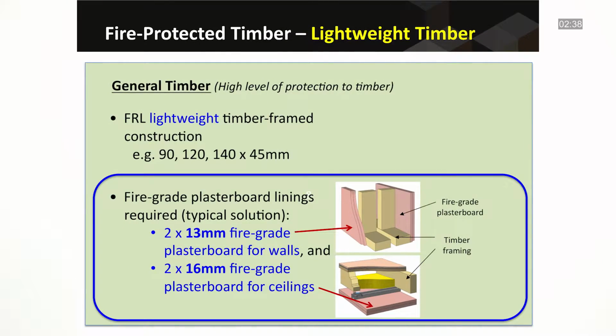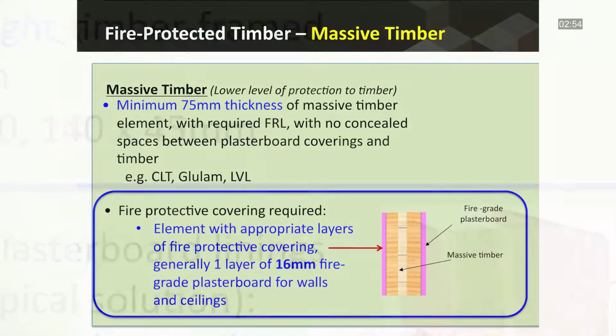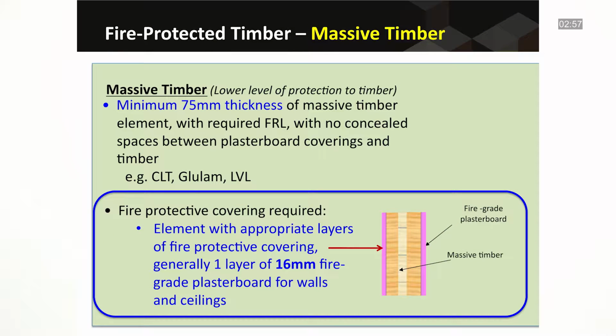Typically for general timber or lightweight timber frame construction, a high level of protection to the timber is required. The DTS provisions require the use of 2 layers of 13mm fire-grade plasterboard for walls and 2 layers of 16mm fire-grade plasterboard for ceilings. For massive timber, such as LVL or CLT, with a minimum of 75mm thickness, a lower level of protection is required. As these are proprietary products, details of specific fire protective covering requirements should be provided by the manufacturer. But in general, this will typically involve 1 layer of 16mm fire-grade plasterboard for both walls and/or ceiling elements.